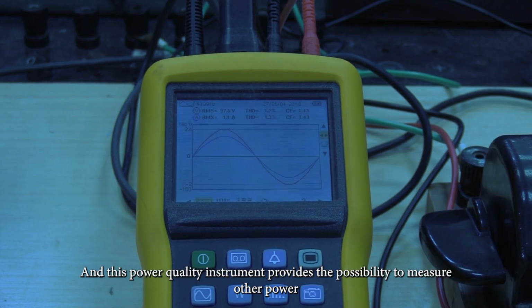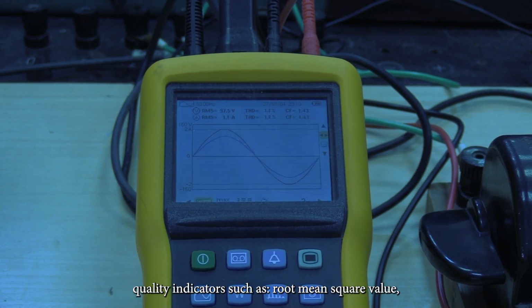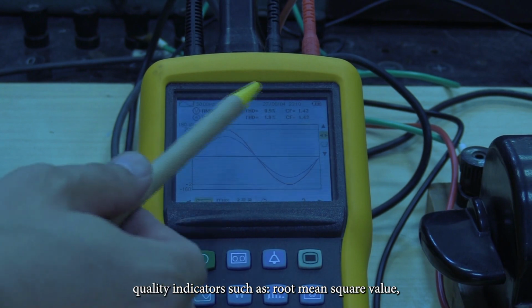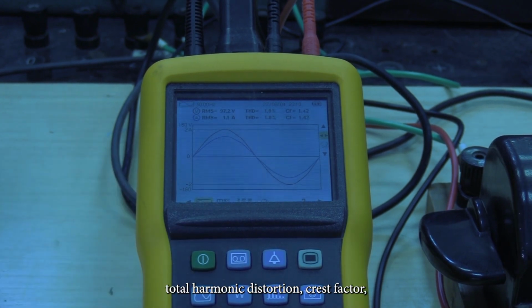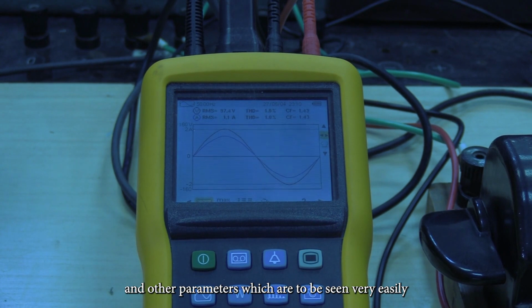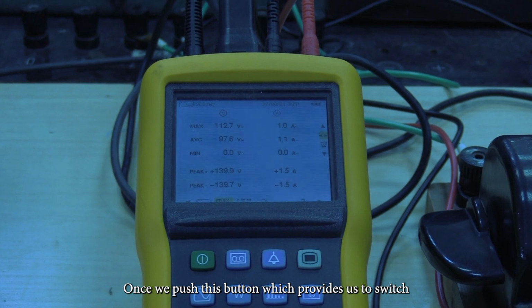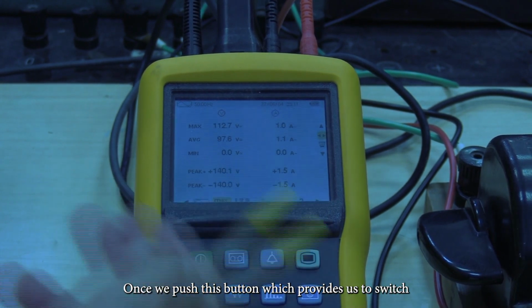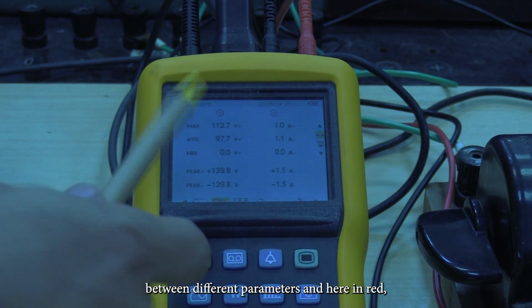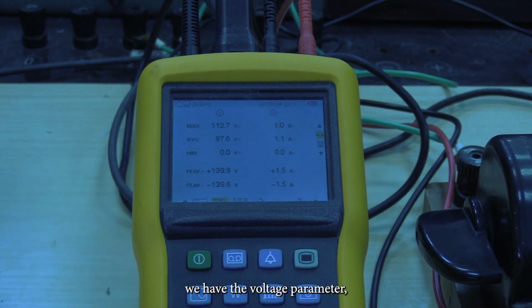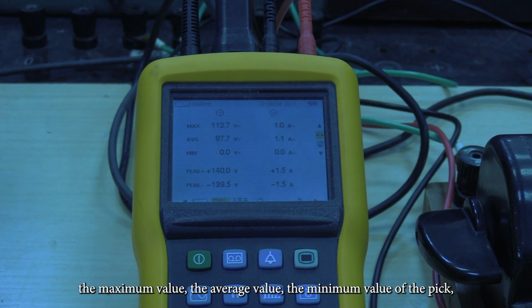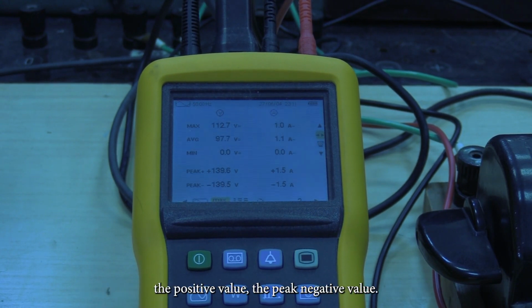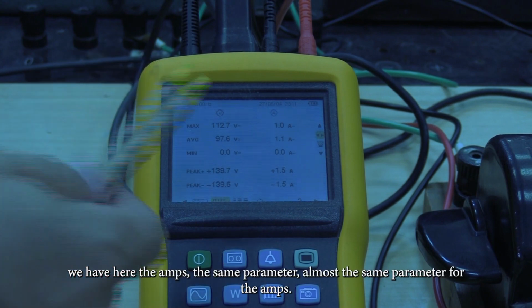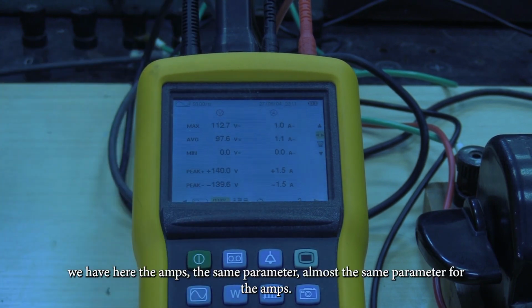And this power quality instrument provides us the possibility to measure other power quality indicators, such as the root mean square value, THD, total harmonic distortion, crest factor, and many other parameters, which can be seen very easily once we push this button, which lets us switch between different parameters. And here, in red, we have the voltage parameters: the maximum value, the average value, the minimal value, the peak positive value, the peak negative value, and also we have almost the same parameters for the amps.